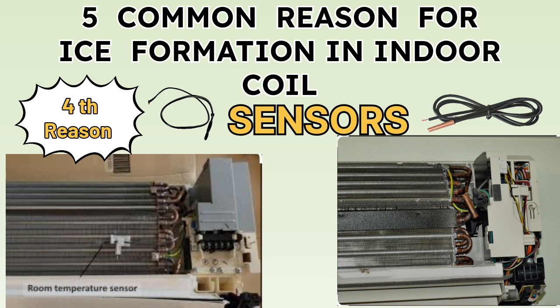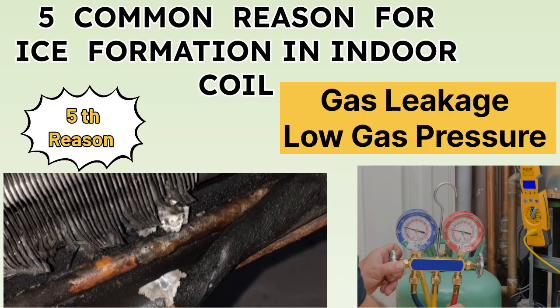The fifth reason is gas or Freon leakage or low refrigerant charge. When we install an AC, if there is a leakage, after some time there will be a lack of refrigerant and ice formation in the indoor unit. As the unit gets older, leakage can also occur. To avoid this, keep the refrigerant pressure normal — for R-410A it should be around 110 to 115 PSI. Check the pressure and there will be no ice formation in your indoor unit.